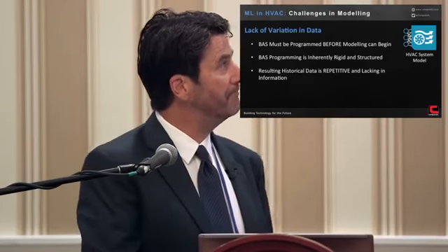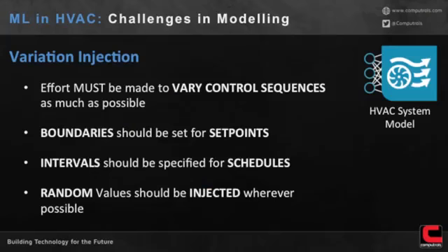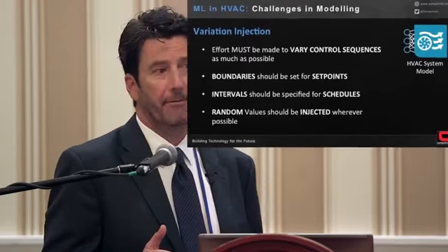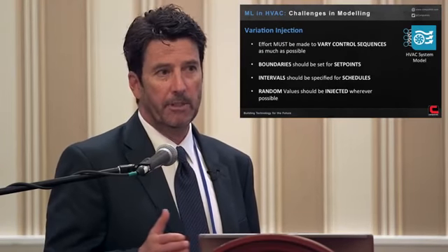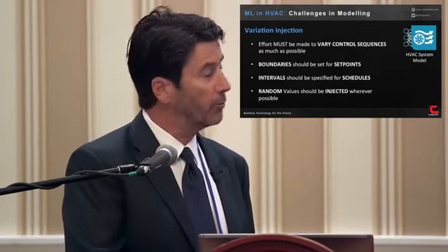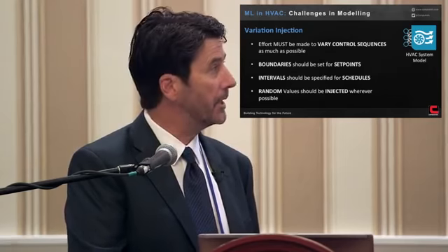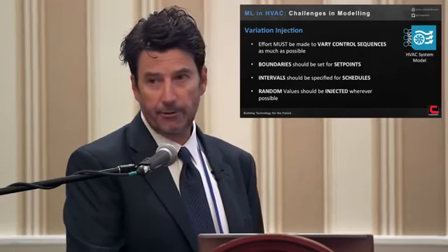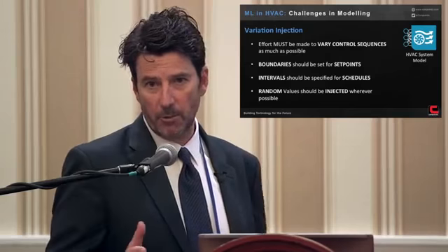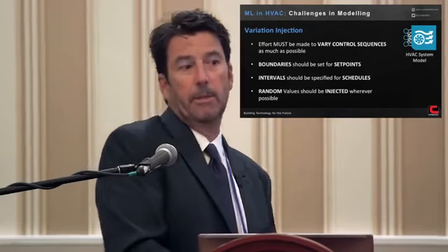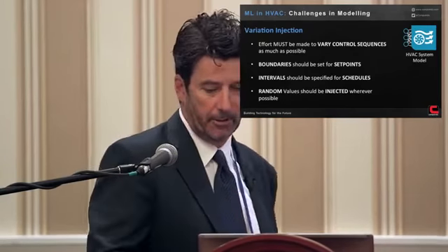So we try to control vary control sequences. We set boundaries, for example, on set points. If I can take a supply air set point and say, well, it's okay if it's 54 degrees or 57 degrees, and I'll randomly modulate in between there, it'll really, really help build that model. Intervals for schedules: on our optimum start, we usually put an interval that has to be on by at least this time, but it can be as early as another time.